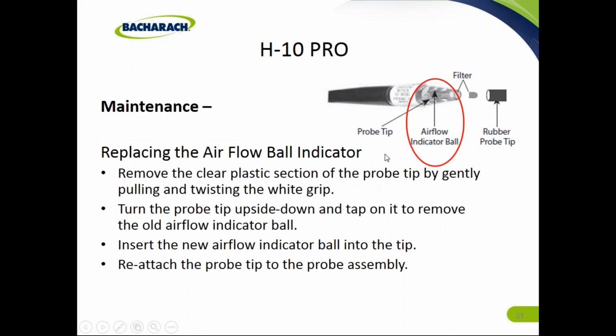The airflow ball, if that's bad, you want to replace it with a new one. Remove the clear plastic section in the probe by gently pulling and twisting. Turn the probe tip upside down and tap it to remove the airflow ball indicator. Insert a new ball indicator into the tip and then reattach the probe into the probe assembly.